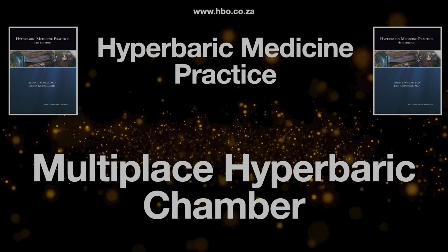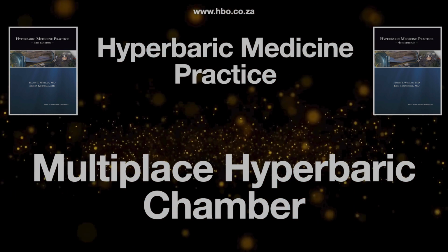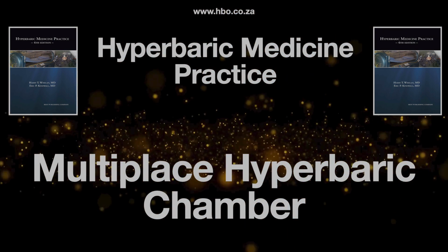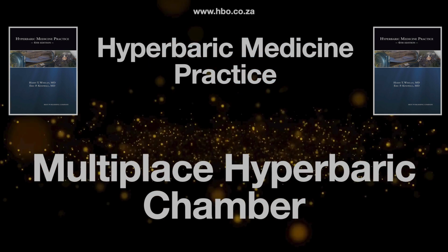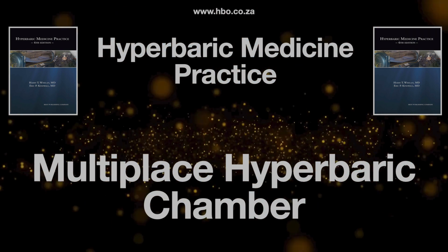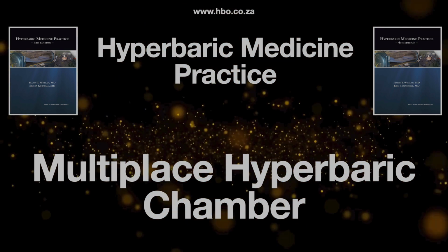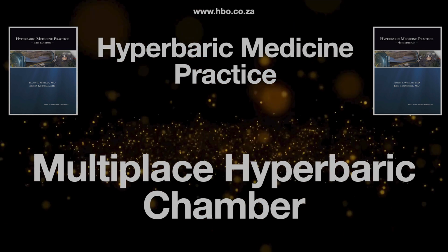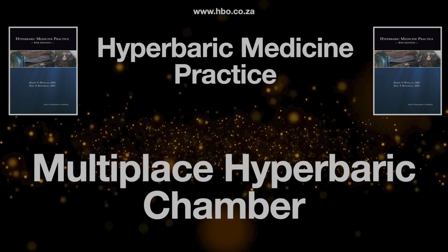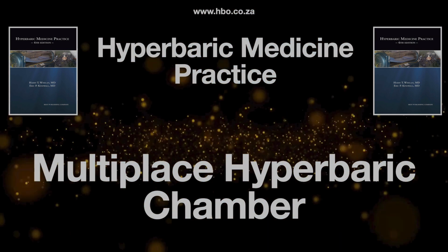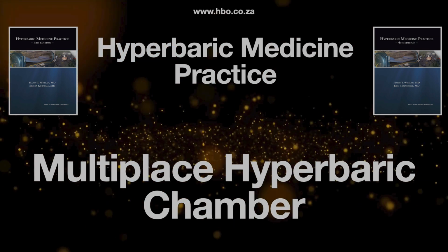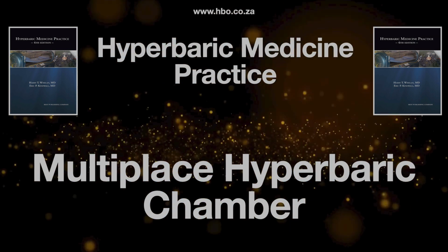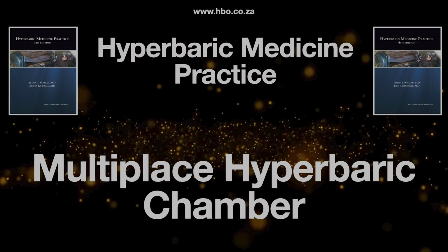If it creeps up past a set limit, usually around 23.5%, the system can automatically switch patients off their oxygen masks and onto just breathing regular medical air through masks to quickly dilute the atmosphere. That's smart. An automatic safety override. Yep. And there are also specific valves designed to physically prevent someone from accidentally flushing pure O2 straight into the chamber. And then you have the water sprinkler system.